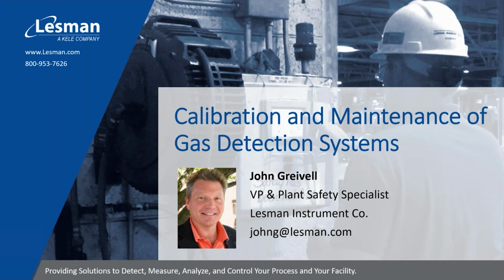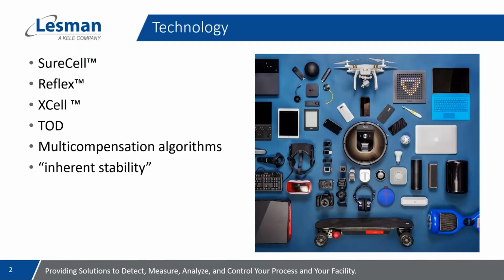Since those days, all sorts of remarkable technology has been developed. Today we've got virtual reality goggles, we've got watches that can tell you that you're about to have a coronary event. So the question is, why can't we use all this technology to figure out how to minimize the amount of time spent on maintaining permanently installed gas detection systems? The reality is, manufacturers have been developing and marketing reduced maintenance technologies for decades. We've got fail-safe optical detectors, improved sensor performance with embedded predictive technologies. Not to mention the procedure for executing calibrations and maintenance has gotten substantially simpler. Even so, you still get monthly, quarterly, or semi-annual work orders for calibration and maintenance.